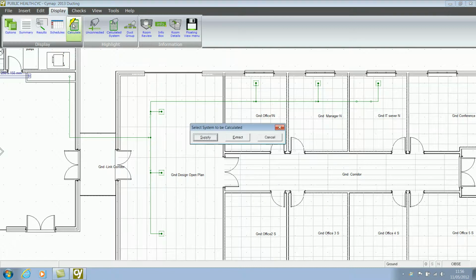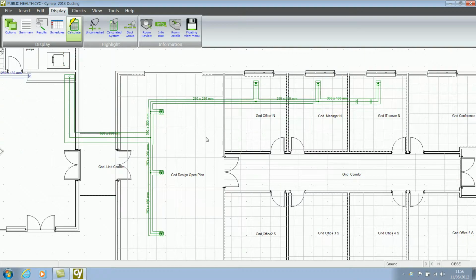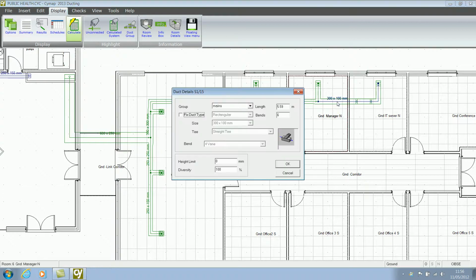Display calculate. Notice the program picks up the fact now we have 2 separate systems. We're actually calculating the supply system, and this again puts our duct information in here. Because I've introduced a set, this has changed the duct size. If I wanted to fix the duct size, I can actually double click on here and pick something more appropriate. It's also squeezed the duct size down somewhat to accommodate it within the ceiling void, so it's given you a slightly different aspect ratio on this duct.